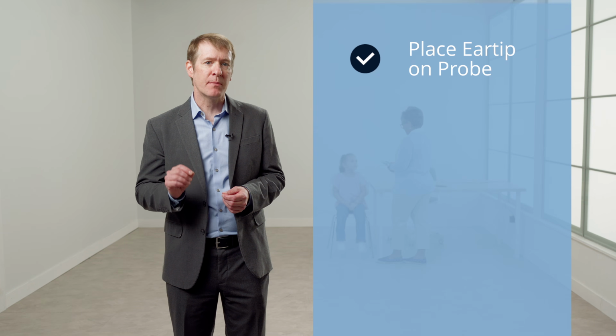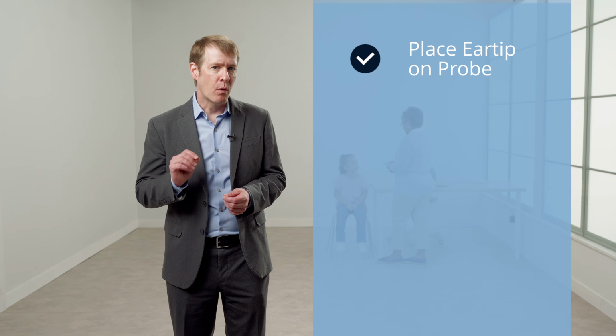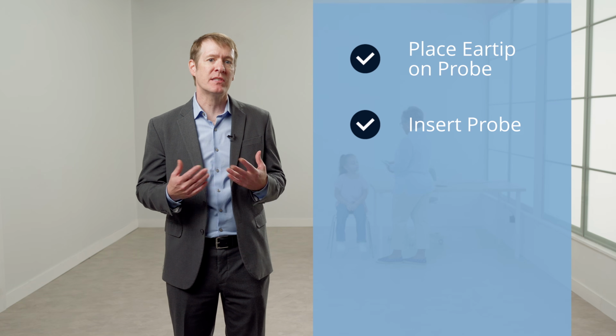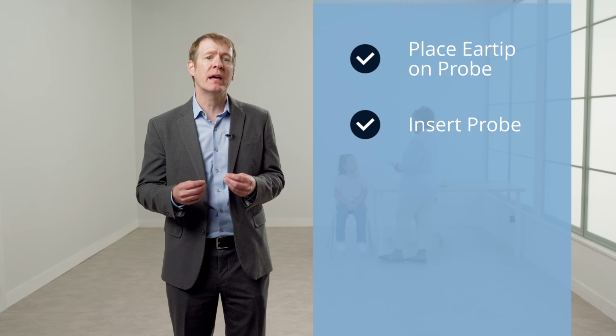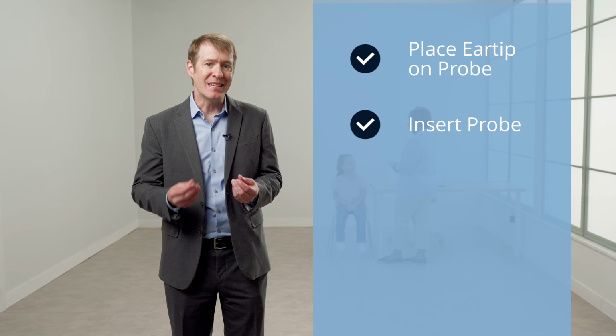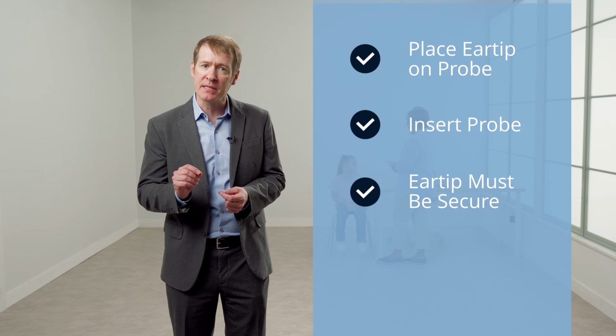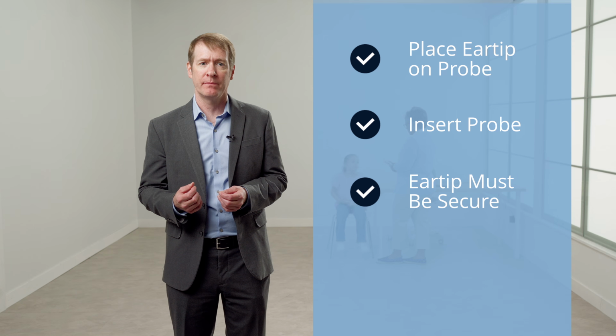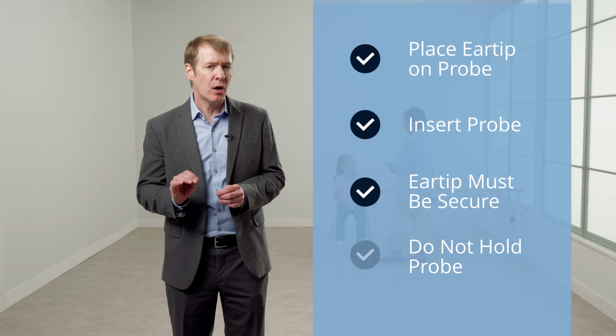For all patient ages, place the ear tip firmly on the probe. Once you have inserted the probe into the patient's ear, make sure that when you let go of the earlobe, the ear tip is still firmly in place and that it will not easily fall out. Do not hold the OAE probe during the measurement because this can introduce noise that may interfere with the testing.